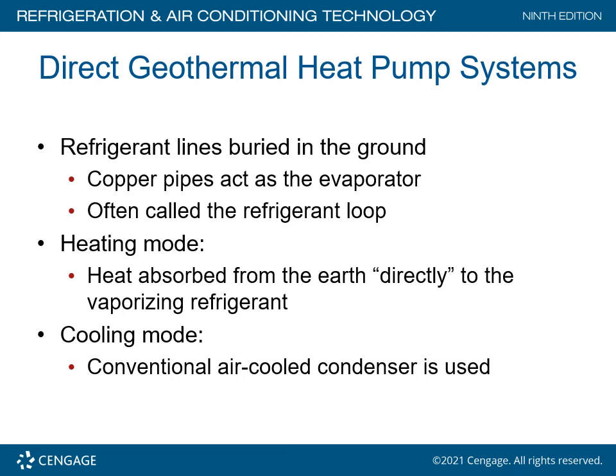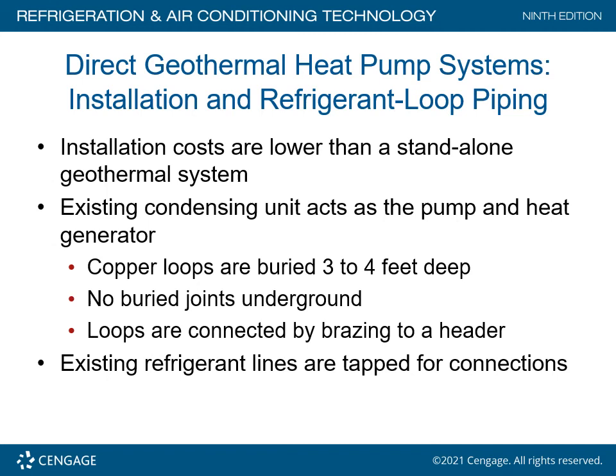In direct geothermal heat pump systems, refrigerant lines are buried in the ground. Copper pipes act as the evaporator — often called a refrigerant loop. In heating mode, heat is absorbed from the earth directly into the vaporizing refrigerant. In cooling mode, a conventional air-cooled condenser is used. Installation costs are lower than stand-alone geothermal systems. Copper loops are buried about three to four feet below ground with no buried joints underground. Loops are connected by brazing to a header, and existing refrigerant lines are tapped for connections. The loop is solid copper in and out.